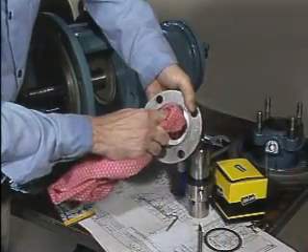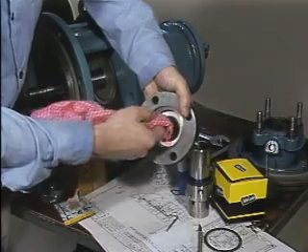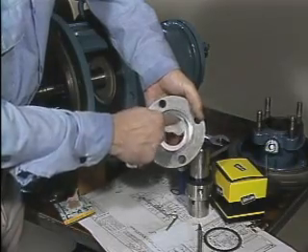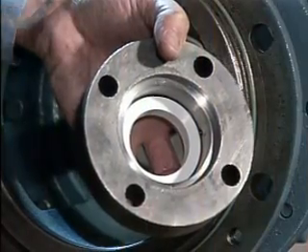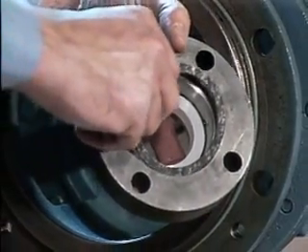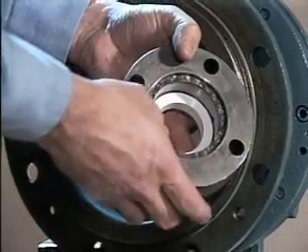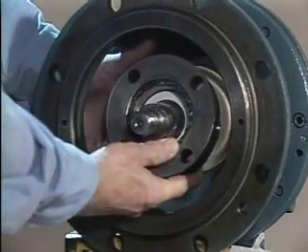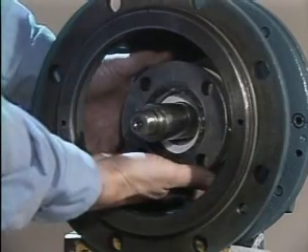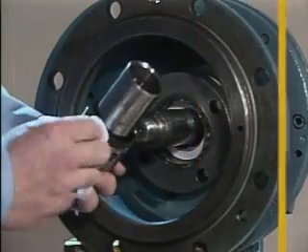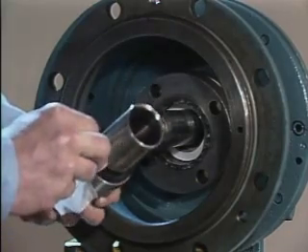After the mating ring is in place, all excess lubricant should be wiped off, and the mating ring face should be cleaned with lens paper and an approved solvent. Then the gasket between the gland plate and the stuffing box is positioned on the gland plate, and the gland plate is slid onto the shaft and pushed back against the bearing housing out of the way. Next, the rotating seal face is wiped clean with lens paper and an approved solvent.